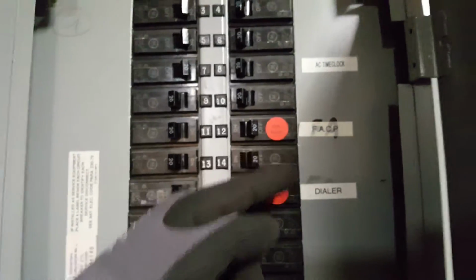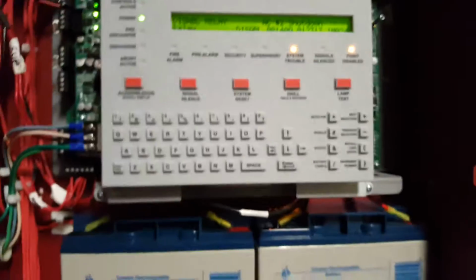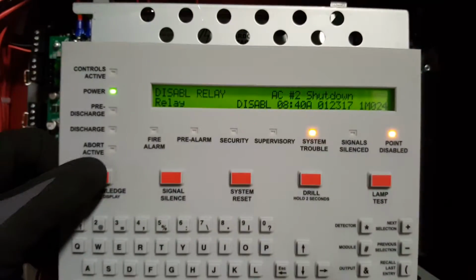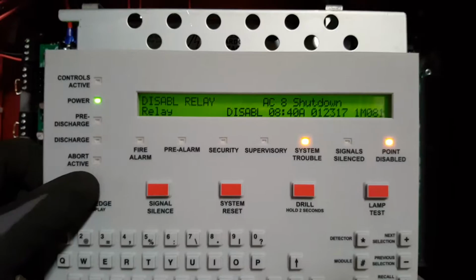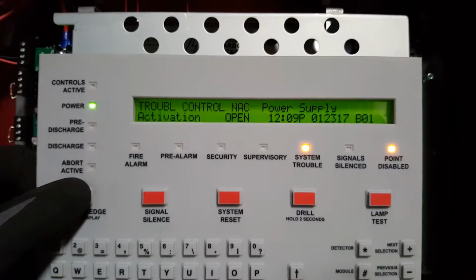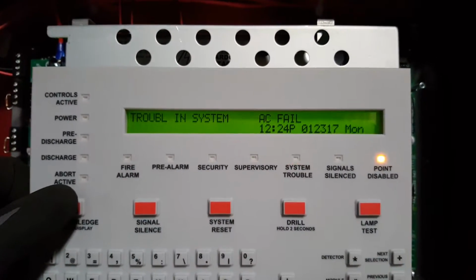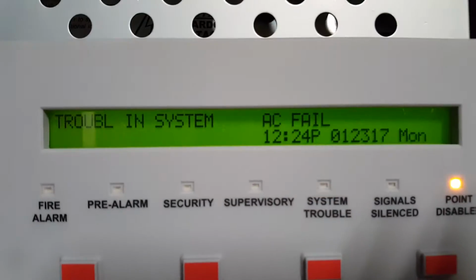And if it gets the trouble. So we're gonna come to the FACP. Flip it. And we're gonna check to see if we got a trouble. There it is, AC fail. So now we got the AC fail. So now the panel is just running off the batteries and it is functioning.